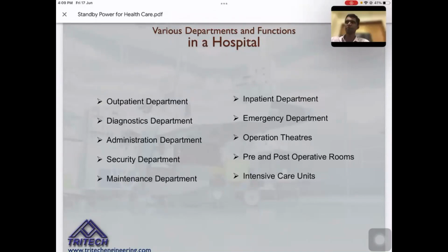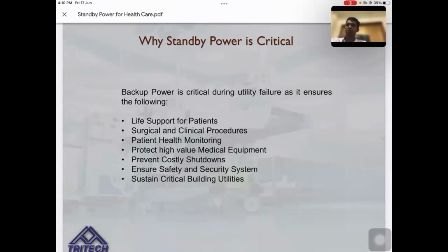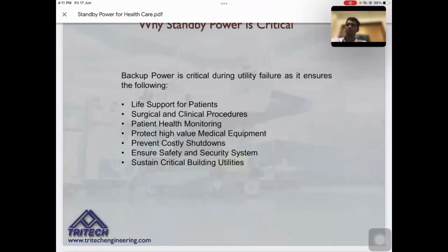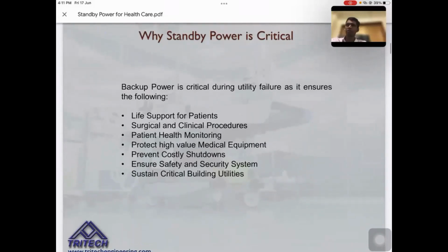So that's the first slide. I just want to show what the departments and functions in a hospital are. These are aspects which need to be taken into consideration for the power distribution as well as the backup systems. And why is standby power critical? Backup power supply is critical because it supports the life support systems for the patient. Every surgical and clinical procedure depends on power. Again, the monitoring of patient health is also part of the power supply system. Apart from this, you also have the high value medical equipment which needs to be correctly protected, and power should not fail, which may result in preventable costs, extremely expensive shutdowns and maintenance. And also, to ensure safety and security systems are working properly, you need power supply. And apart from this, you also have the critical building services, which need to be maintained during power outages.